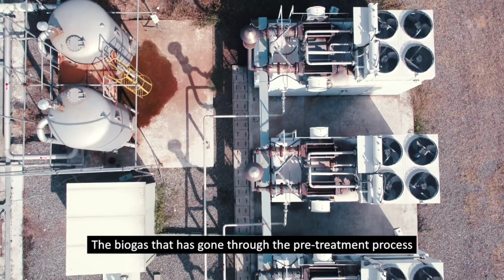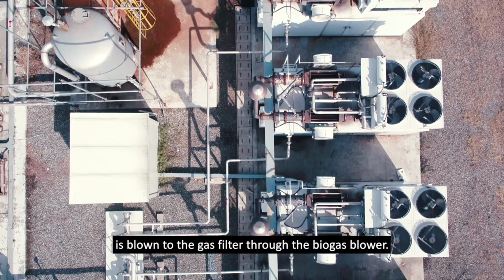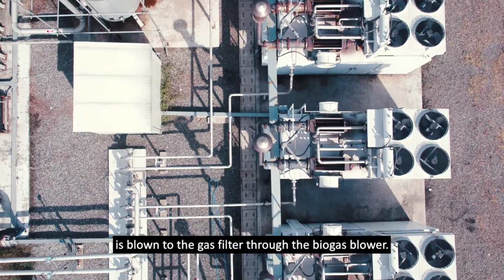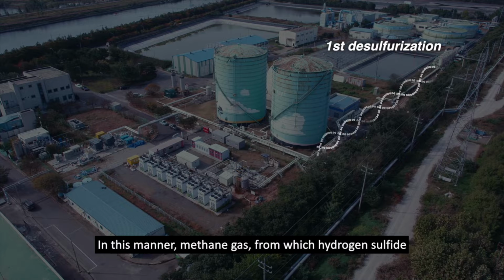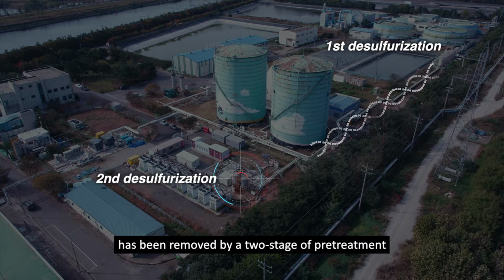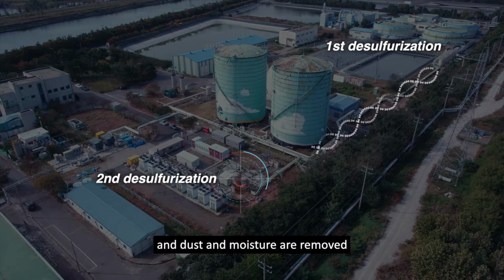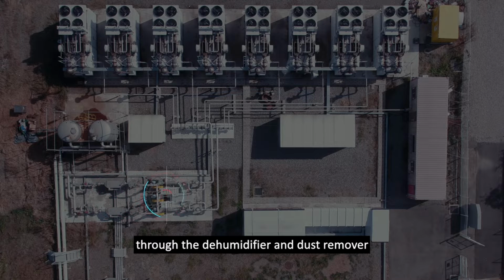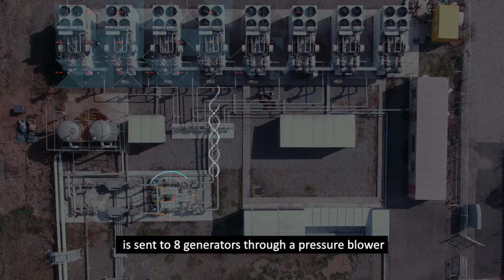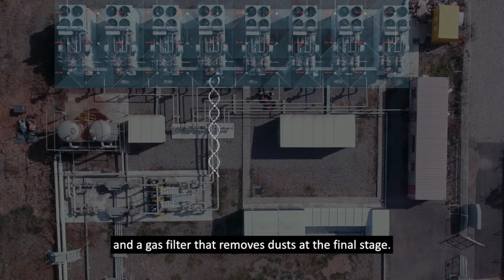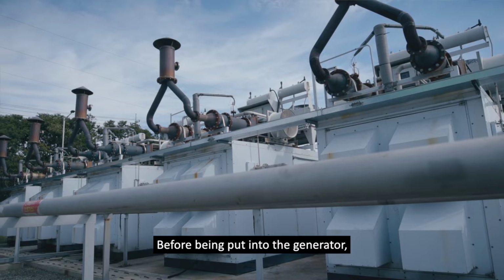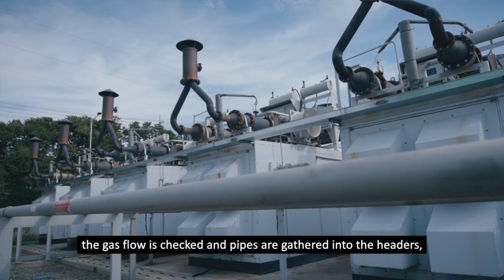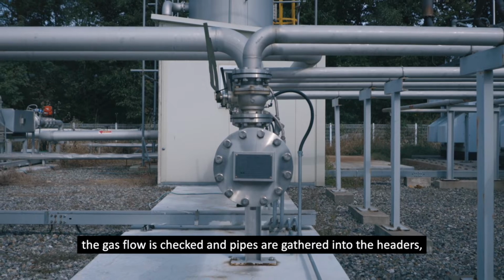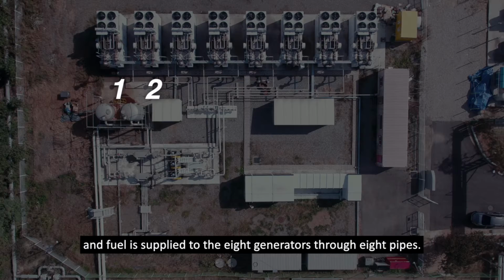The biogas that has gone through the pretreatment process is blown to the gas filter through the biogas blower. In this manner, methane gas, from which hydrogen sulfide has been removed by 2 stages of pretreatment, and dust and moisture are removed through the dehumidifier and dust remover, is sent to 8 generators through a pressure blower and a gas filter that removes dust at the final stage. Before being put into the generator, the gas flow is checked and pipes are gathered into the headers. Fuel is supplied to the 8 generators through 8 pipes.